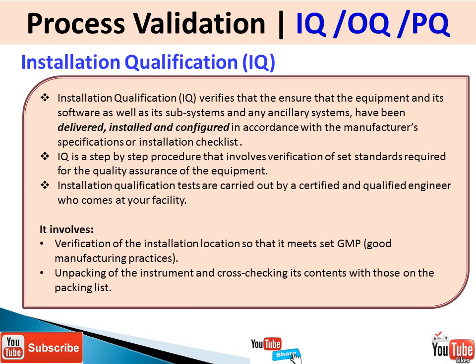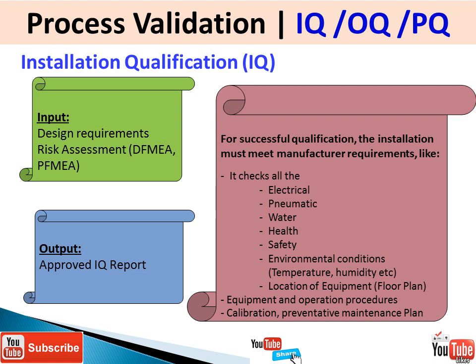IQ has to meet certain GMP requirements — good manufacturing practices — and involves checking the packing of the instrument and cross-checking its content against the packing list. The inputs include design requirements such as DFMEA (design failure mode and effect analysis) and PFMEA (process failure mode and effect analysis). The output is an approved IQ report. During IQ, we check all electrical and pneumatic connections, water requirements, health and safety conditions, environmental conditions like temperature and humidity, equipment location, floor plan, operating procedures, calibrations, and preventive maintenance plans.